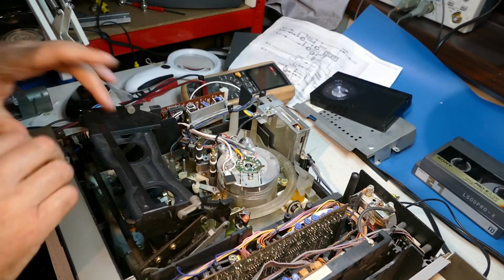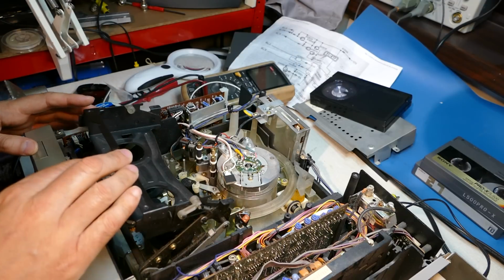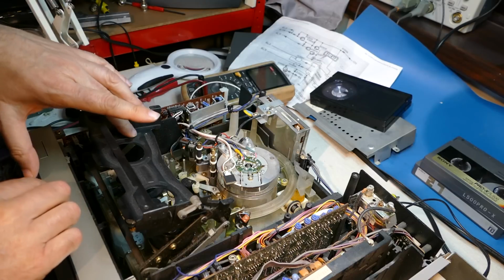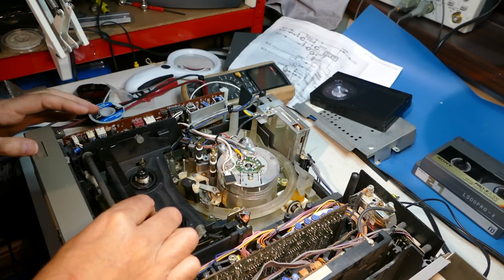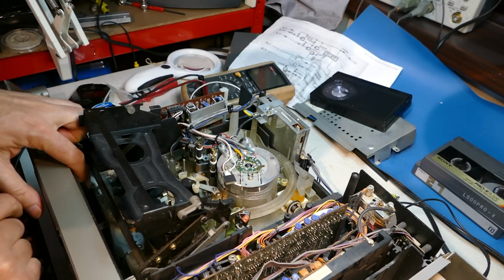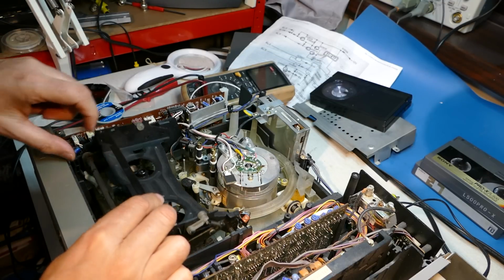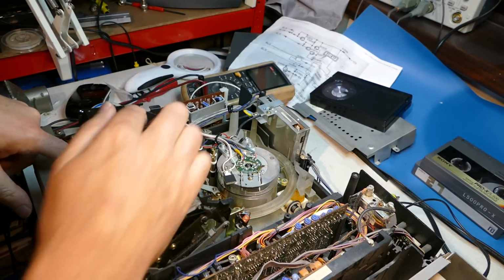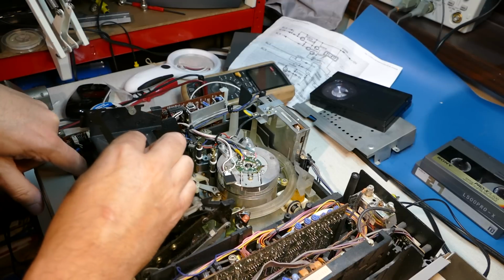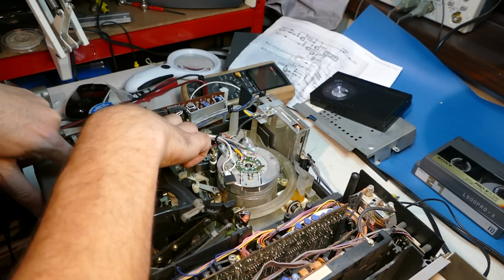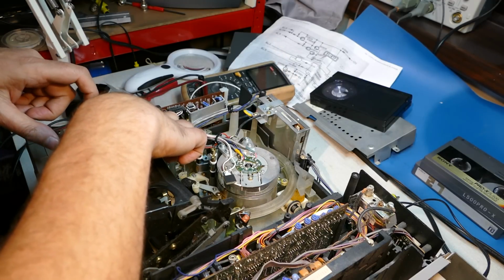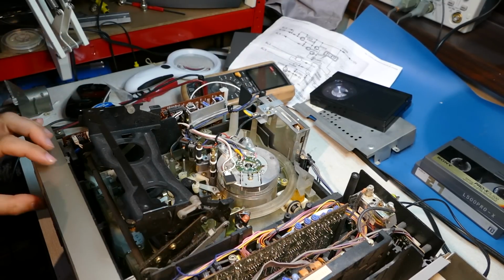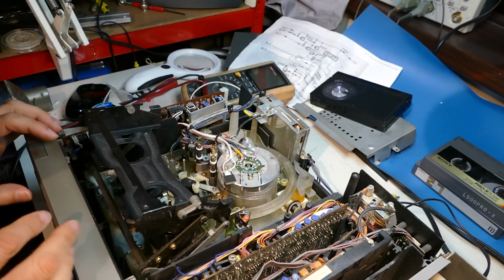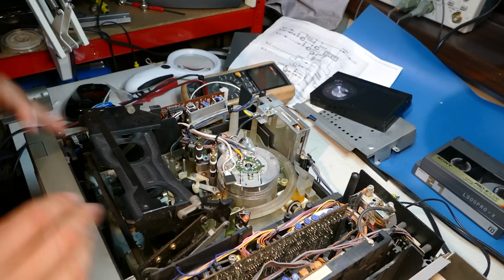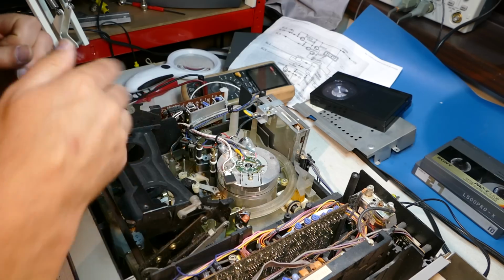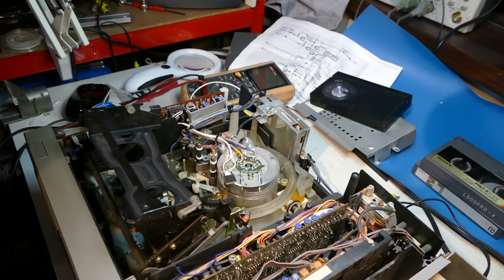Now, I've been working this with the cassette carriage in, but you can even go as far as taking the cassette carriage completely out. To do that you need to fool two parts of the mechanism: one to say there's a cassette in, which is this, and the other that the cassette carriage is down, which is this thing here. You'd need to simultaneously pull that forward and push this down while the carriage is out, and you can make the machine think there's a cassette in there - in fact I just did. So now the cassette carriage is up, or could be completely removed, and the machine still thinks there's a cassette in. That's a great way to do debugging: if you've got a problem with the reel drive, reel tables, or lacing, you can exercise the whole machine with no cassette in there, which is really handy.